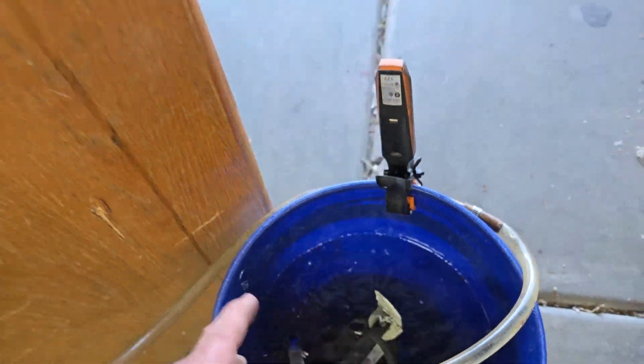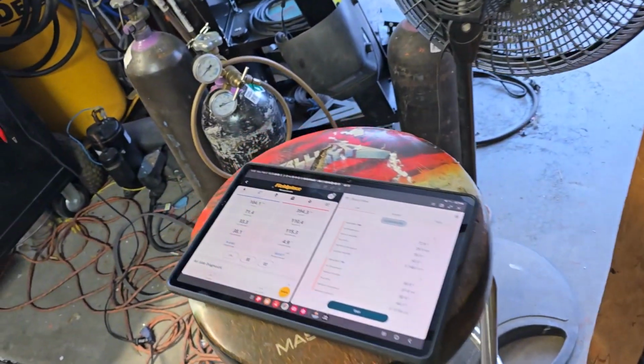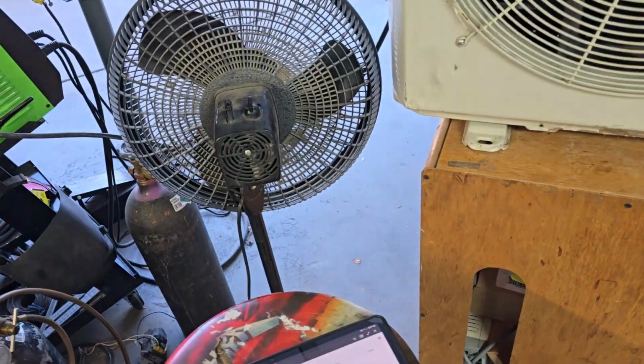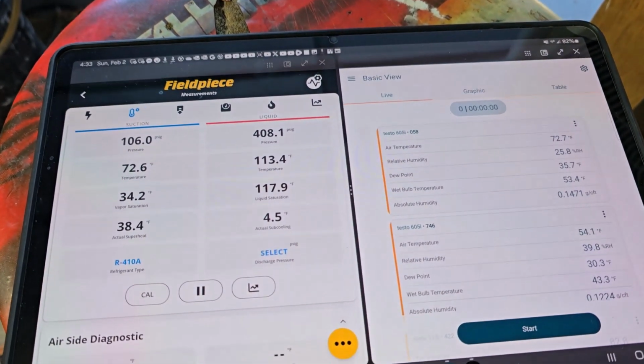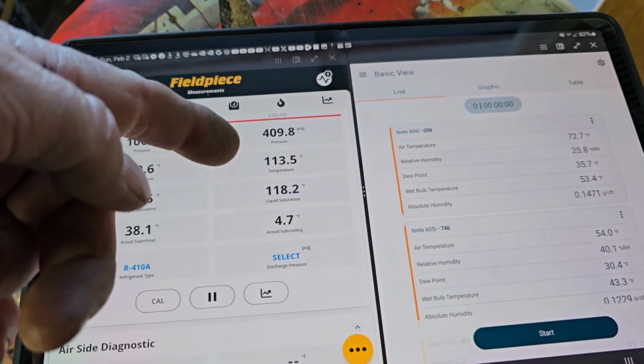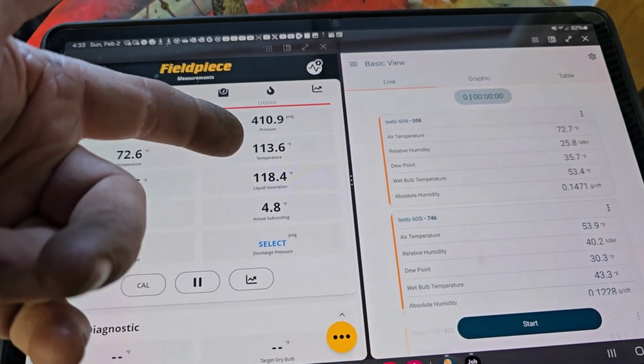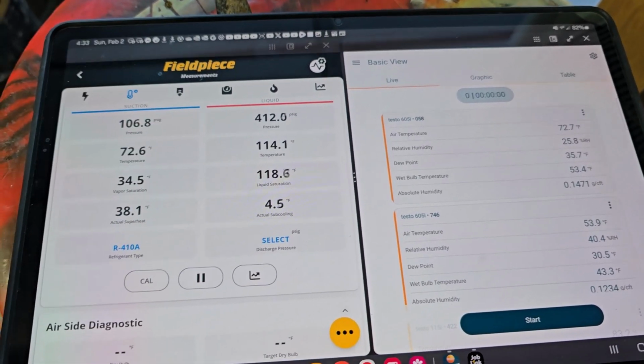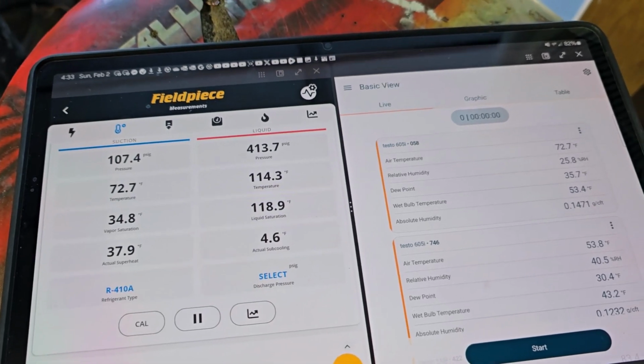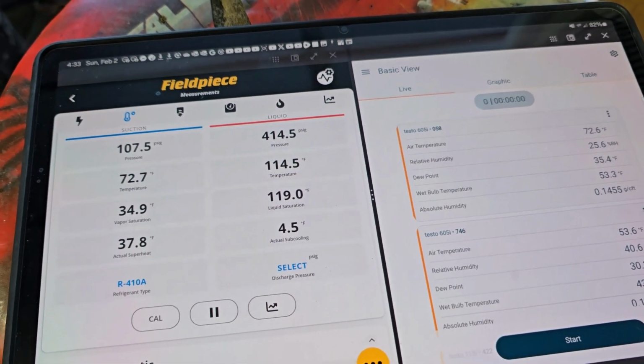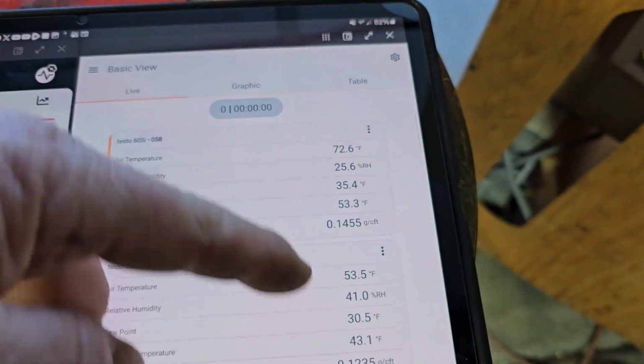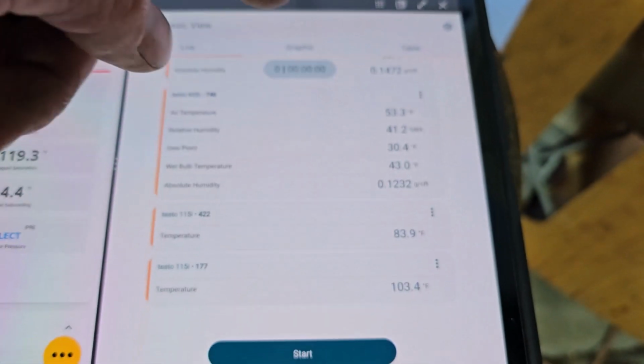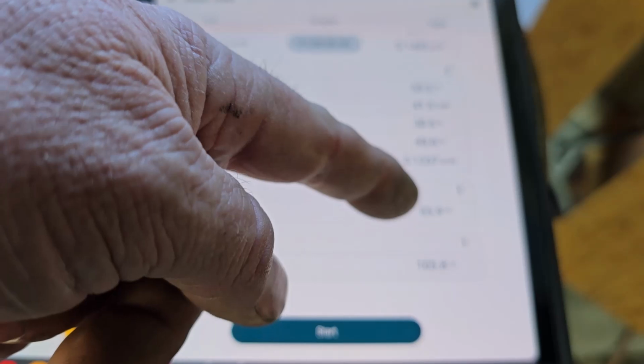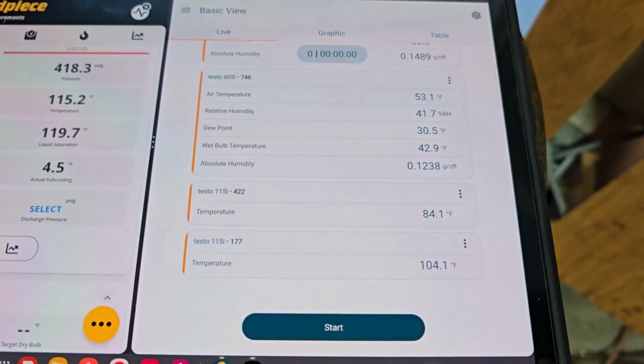Water's flowing. And usually, what I do with my control is I cycle the pump. So my existing heat pump that I have built, it kicks on the pump at over 100 degrees liquid line temperature, and then it goes to high on 110. And it always gets me pretty hot water leaving. So right now, got a 20-degree split approaching on the air already, and you see 83-degree water with a 104-degree leaving.